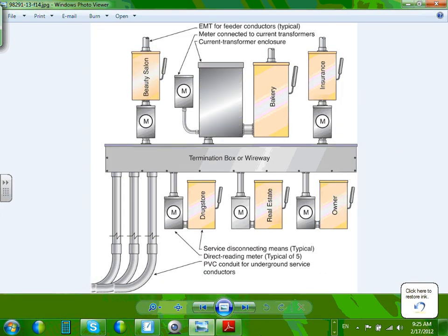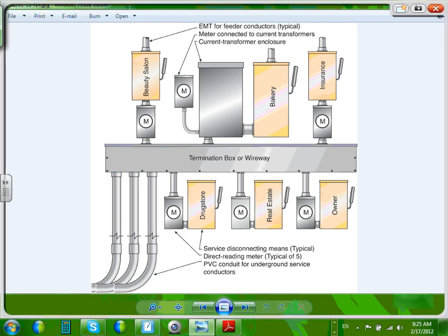Here's the project that we have, guys. This is a poor man's job design, or actually an economical design for a multi-occupancy building. You bring a feeder and you tap it. You tap these feeders to feed a multi-occupancy building, literally, physically tap it. So that's the building that we have. We have 1, 2, 3, 4, 5, 6 feeders coming out of that feed.